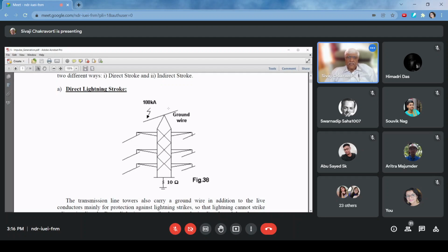Then this lightning goes to earth through the tower, and at the base of the tower there is definitely a certain resistance. It's never zero, right? Any conductor that touches the earth, its resistance doesn't become zero. So this is typically called tower footing resistance. This will be low, varying between 5 ohm and 10 ohm. So what happens? I'm not going into that.